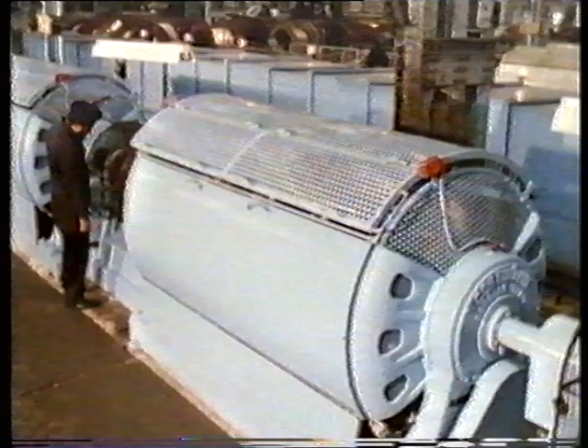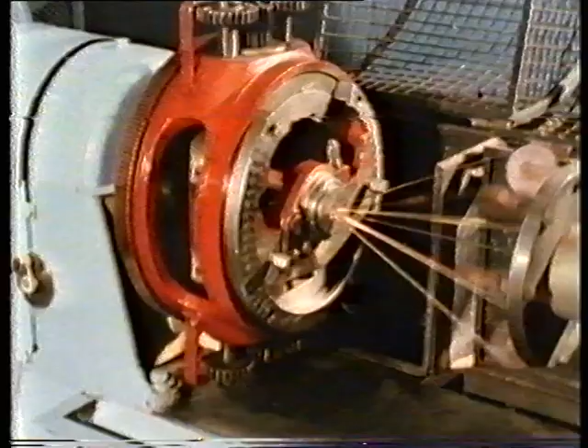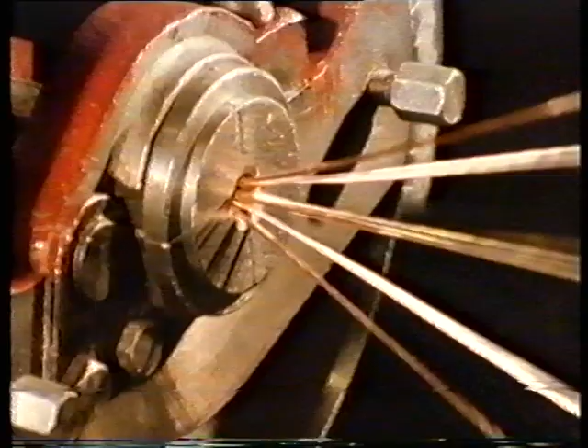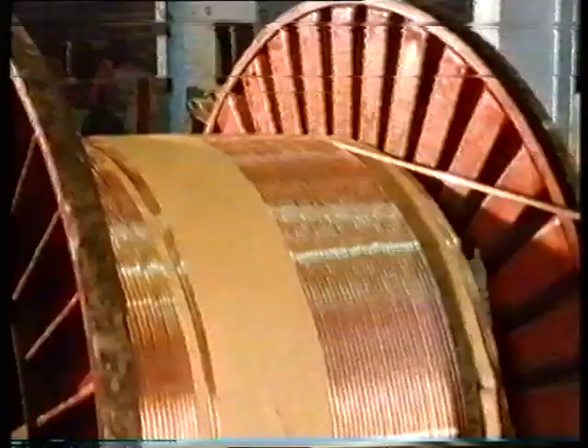The copper conductors start life as lengths of wire drawn down to the required size, in this case 1.85 millimeters. These are then stranded together to form the conductor, a giant weaving process, criss-crossing the wires around a single central strand to build up to 19 altogether. All 3 conductors for the cable are made in this way and then coiled onto a drum.